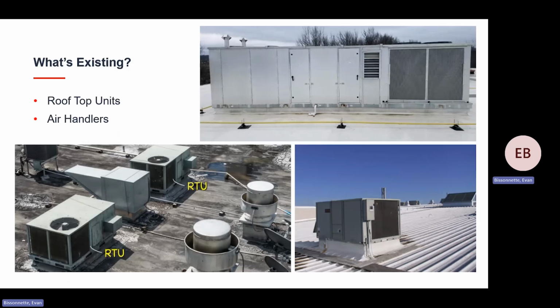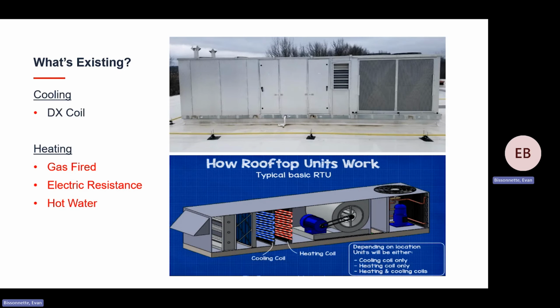So in other instances, like large gymnasiums or auditoriums, you're probably more likely to see a rooftop unit or air handling unit. These are able to process high amounts of ventilation air and produce large capacities to serve these large types of spaces. The issue with most of these rooftop unit systems is they traditionally either have gas-fired heating or have hot water heating coils that are fed from gas-fired boilers. So there's a ton of gas used in these types of systems, or they have electric resistance heat, which is just terribly inefficient compared to a heat pump style system.